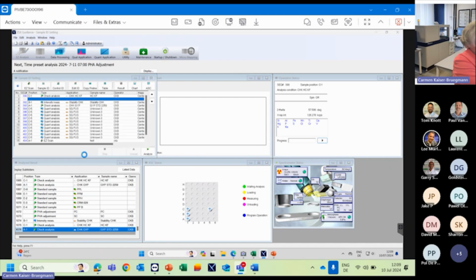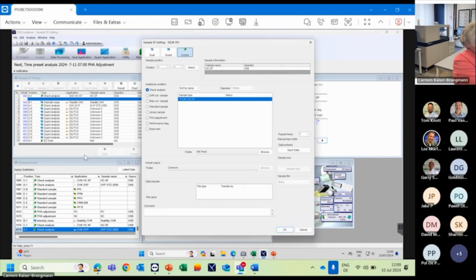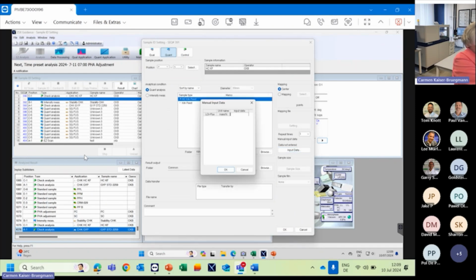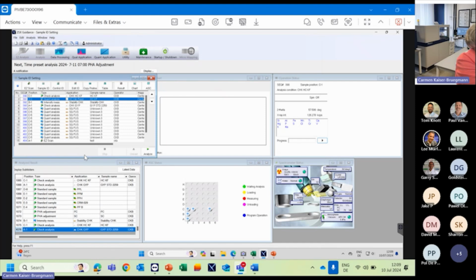So we could say we would like to have this sample from a quantitative method. Here we would put in an input because the method was created like this. So this is a loss on ignition. And of course, we've now inserted a sample in the batch. And additionally, we can call it and say we would like to have a priority analysis. So here you can see the priority button over here. And then, of course, we've now prioritized this over the big batch of samples. Instead of stopping the measurement, we can do this and interrupt in such a way.